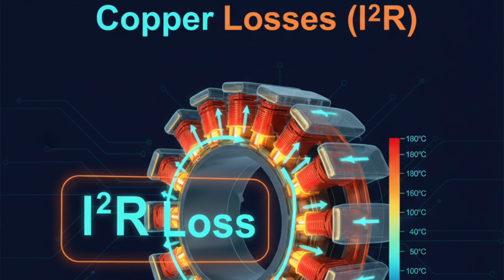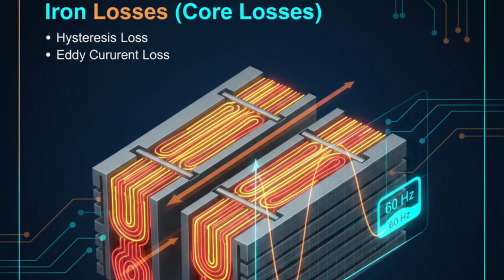These losses convert electrical energy into heat, raising the temperature of windings and insulation. Excessive copper loss may indicate overloading, shorted turns, poor ventilation, or cooling system failure. In marine practice, engineers continuously monitor winding temperature sensors and insulation resistance values to ensure safe operation and to prevent costly breakdowns during voyages.